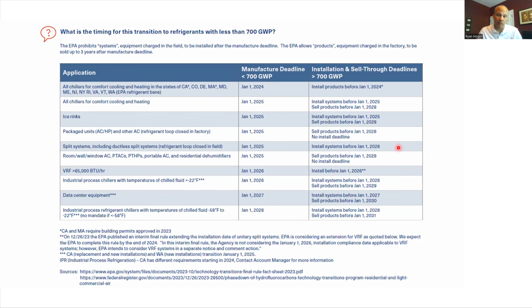If you're looking for a loophole, you're probably not going to find it, because A, the chance of you being able to get your hands on a new 410A evaporator and a new 410A condensing unit, both that fit each other, is low. And even if you do, legally, you cannot install them even like a day apart. I mean, I guess you could. You could install the condensing unit, pipe it up to the old evaporator, charge it, and run it. Then you can come back the next day and cut the evaporator out, pipe the new one in, charge it, and run it. Right? But you can't install them and not charge it and run it. So I know you guys are looking for a loophole. You're probably not going to find it unless you want to cheat, just straight cheat.